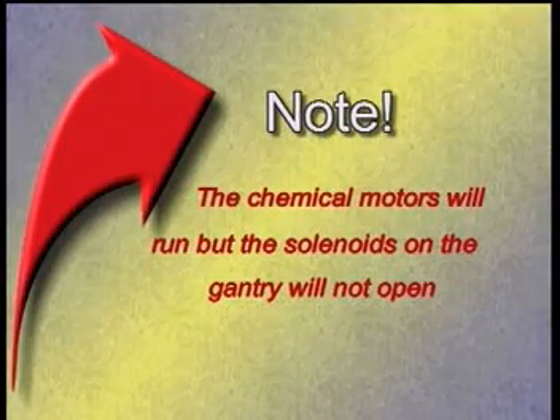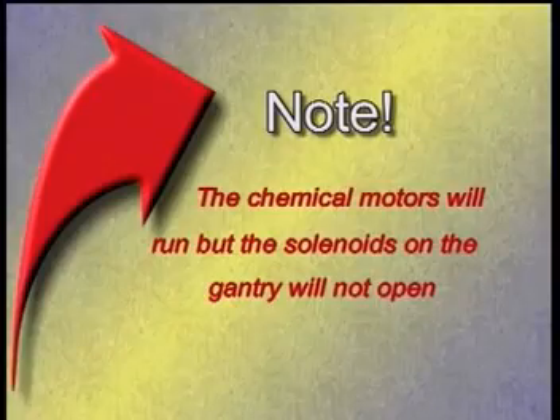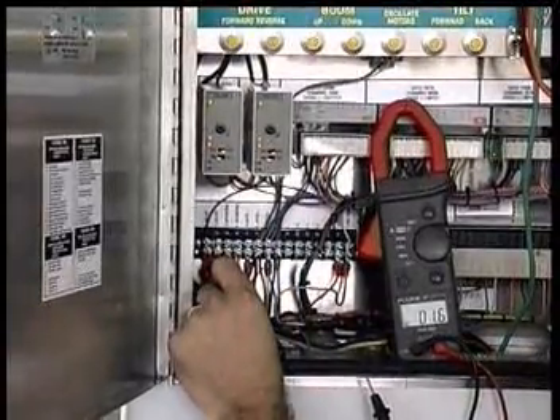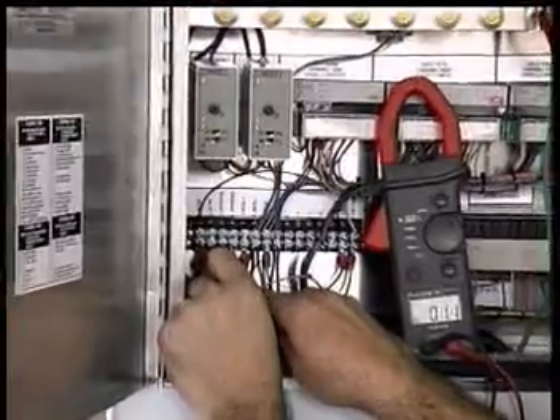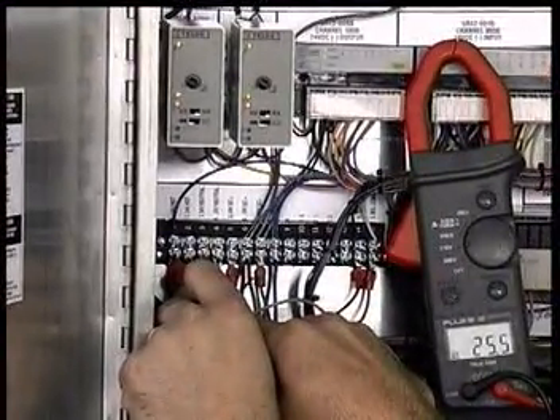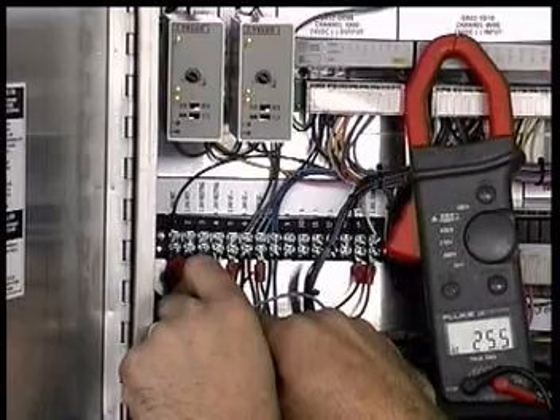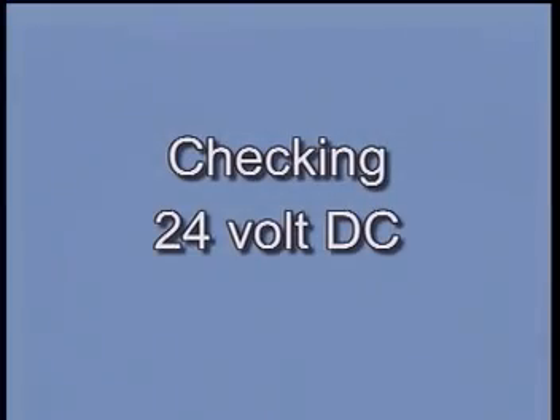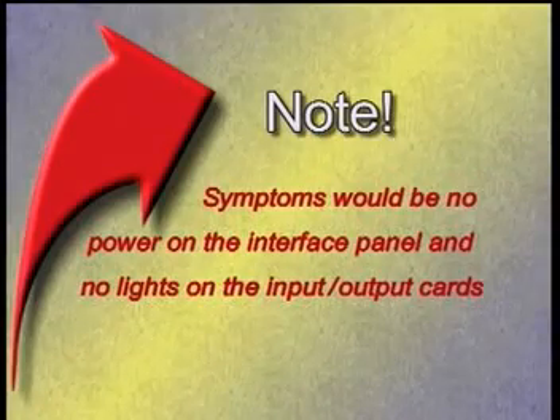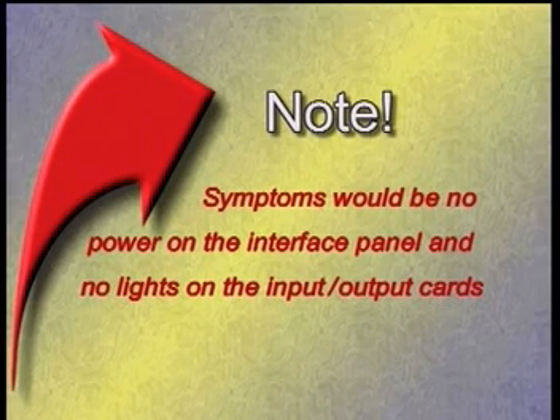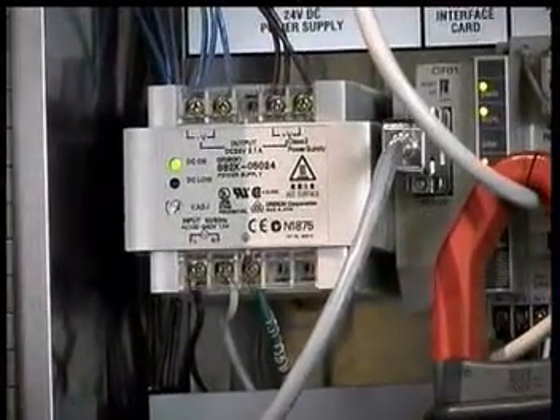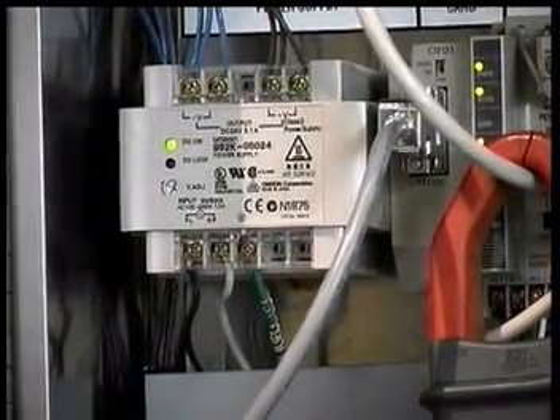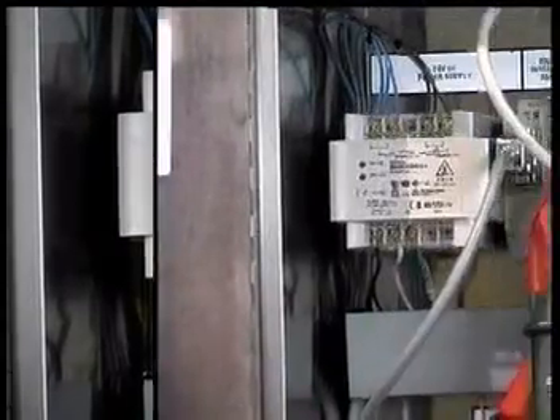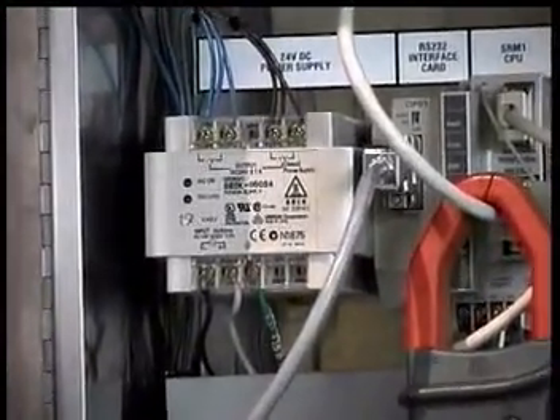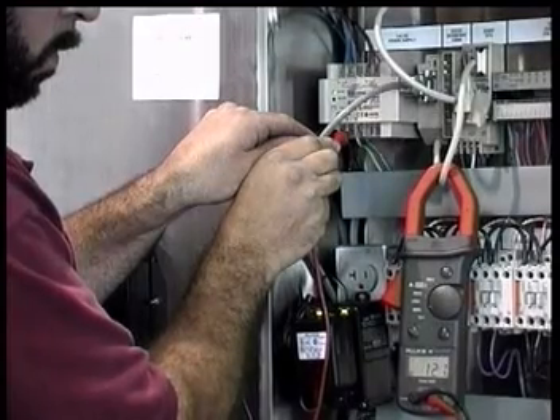If the chemical motors will run but the solenoids on the gantry will not open, check for power at terminals 1 and 3 in the gantry control panel. If power is not present, the problem is likely a damaged SO cord between the equipment room and gantry. Symptoms would be no power on the interface panel and no lights on the input-output cards. Begin by checking for a green light on the DC power supply located in the upper left-hand corner of the control panel. If the light is not on, verify 110 incoming power between terminals L and N.